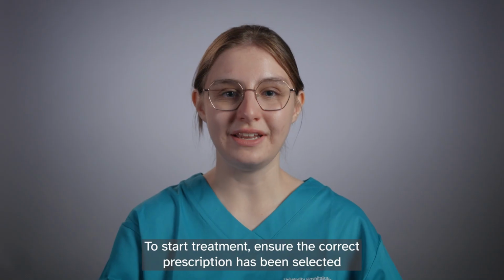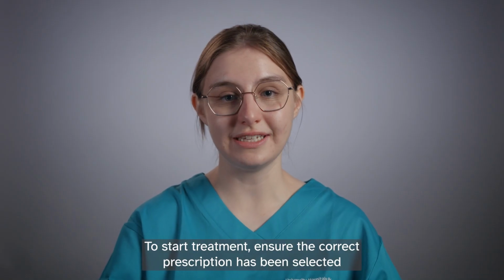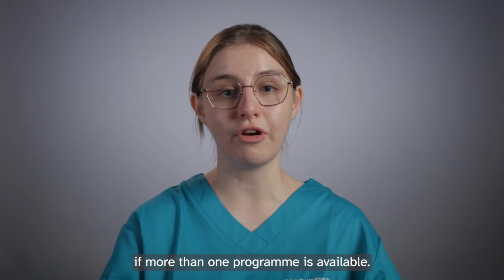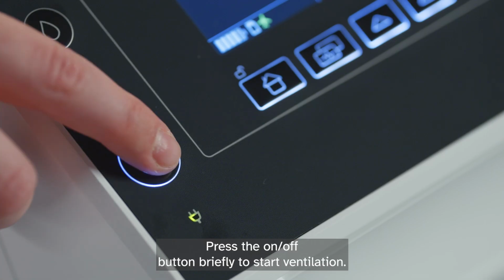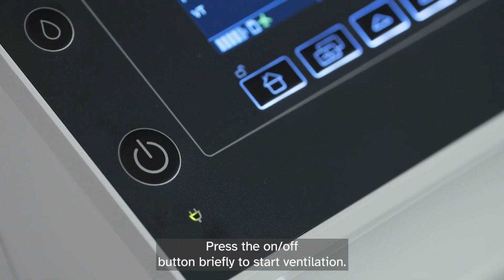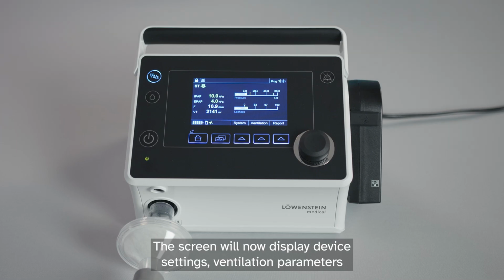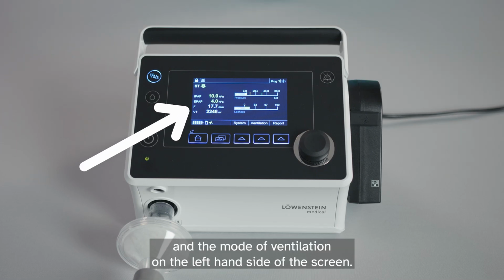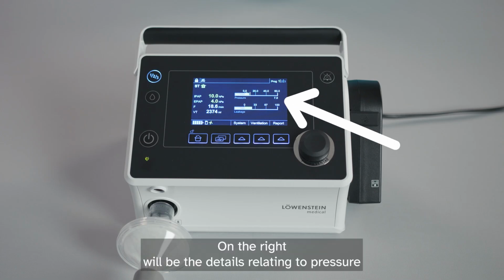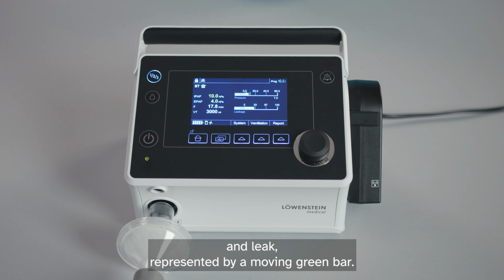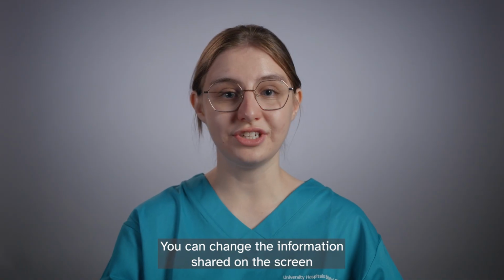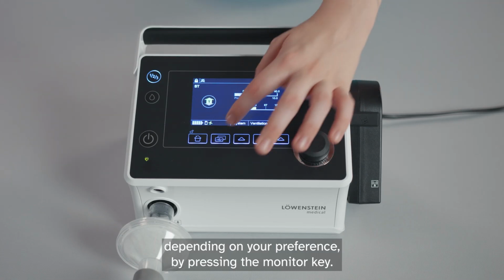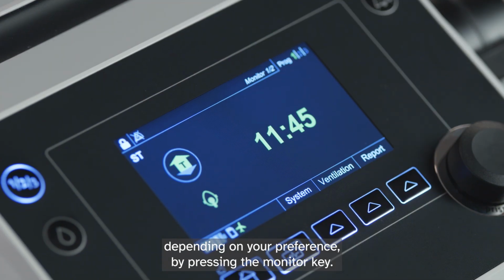To start treatment, ensure the correct prescription has been selected if more than one program is available. Press the on-off button briefly to start ventilation. The screen will now display device settings, ventilation parameters, and the mode of ventilation on the left-hand side of the screen. On the right will be the details relating to pressure and leak, represented by a moving green bar. You can change the information shared on the screen, depending on your preference, by pressing the monitor key.